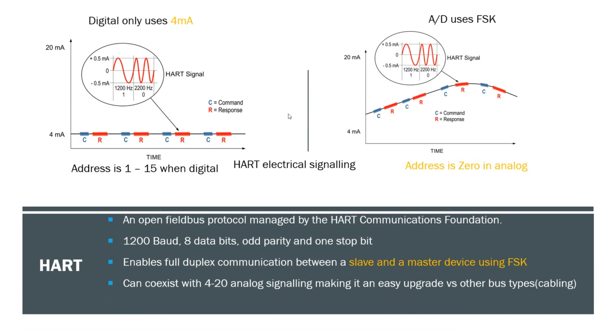Between these two images, this represents digital-only signaling, which means the 4 milliamp value never actually changes—this is the amount of draw the transmitter uses as it operates, and the data is contained within the little packets of information you see here. In the analog or hybrid version, the milliamp voltage changes, and these packets are used basically just for diagnostics, with the measurement value being this analog milliamp value here. So digital-only requires 4 milliamps basically to keep it running.